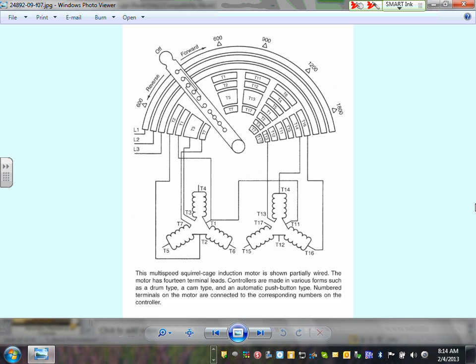When you go to multi-speed motors, they're designed to run at different speeds, 4 speeds. So they can go forward and reverse. You can have this one, 1, 2, 3, 4, 5, almost 5 speeds or 4 speeds. But you can reverse. In reverse, you can go 600. So here's how you get that: by sliding this arm, guys, you connect and disconnect certain coils. I'm not going to get into the details of which coils, and then you basically alter the number of poles, and when you alter the number of poles, you alter the speed of the motor.